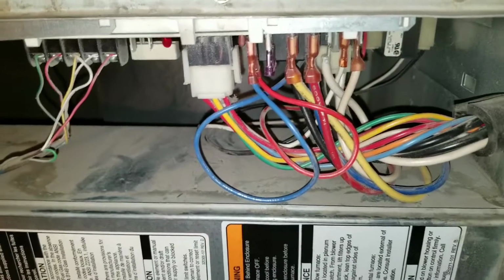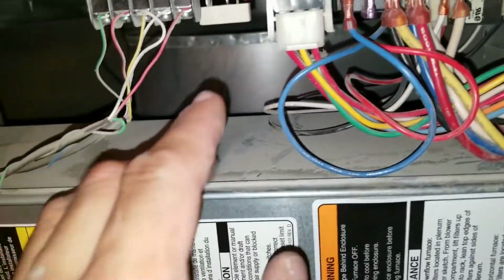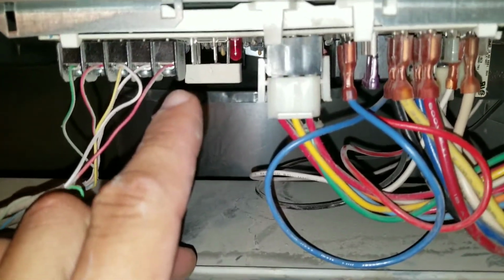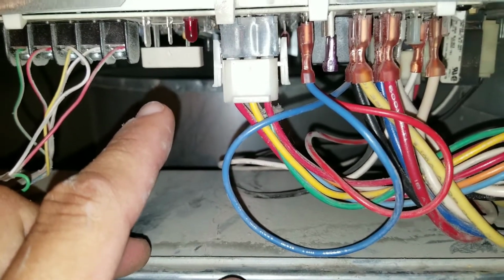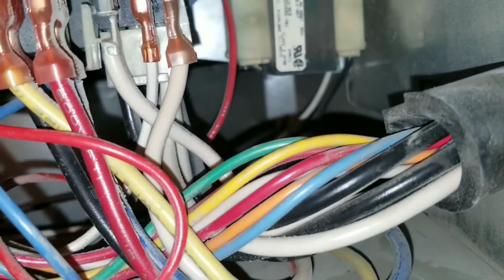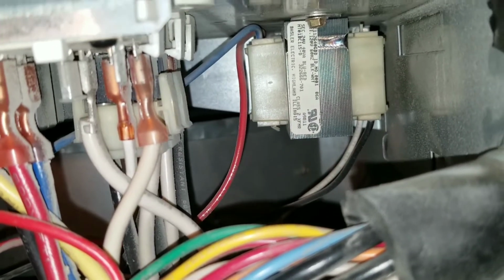So here, I just want to make sure, obviously the board is lit, so I know that I do have low voltage coming in from my transformer. This is my transformer in the back. I have my voltage coming in, 120 volts. That's going to be the black and the white lead, if you see right there. And then I have my blue and my red. That's going to be my low voltage wiring.